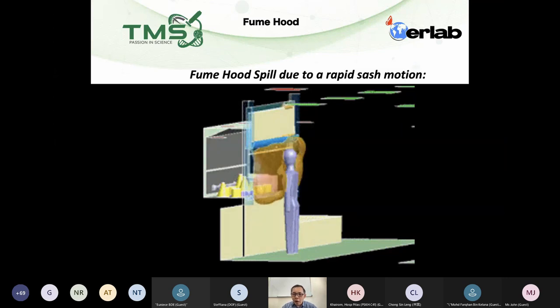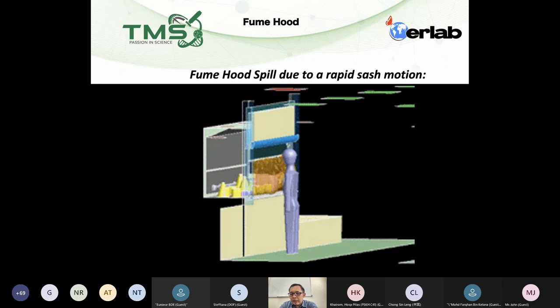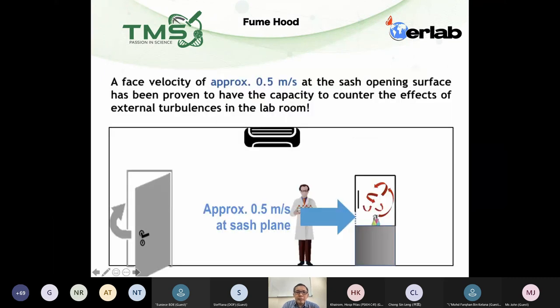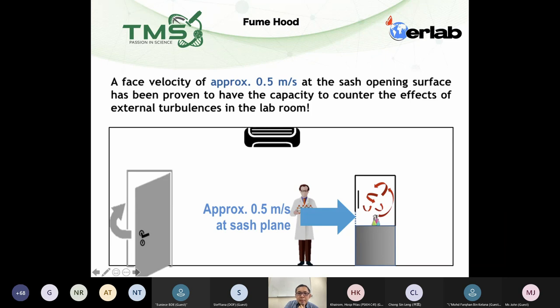Another situation to avoid is opening your sash too quickly — the chemical will be directly exposed to you, especially if you exceed the safe level. With 0.5 to 1 meter per second face velocity, you are safe in normal situations of opening and closing doors, since the room pressure change is minor. Air conditioning will also not cause chemical leakage if you have 0.5 m/s.